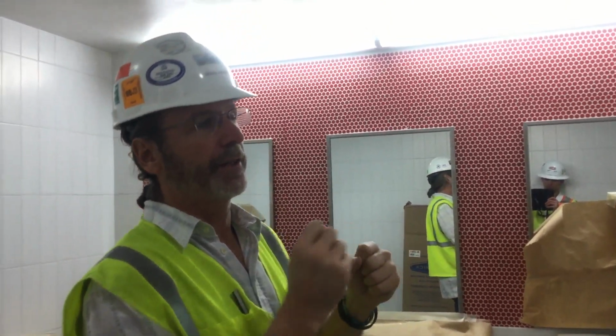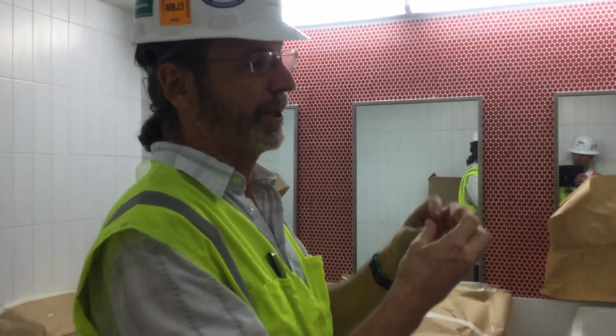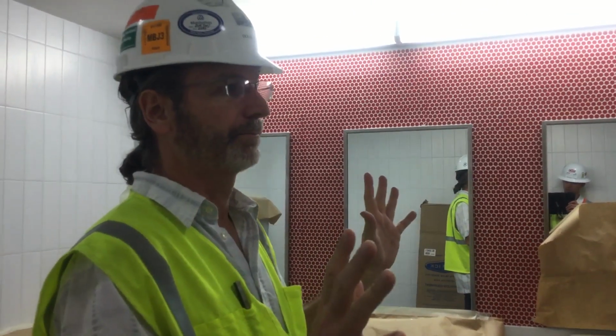That relay puts out - is there a light switch in the restroom? Yeah, that relay feeds to a standard toggle switch and then goes out, so the circuit's a little different. If the switch is on, the sensors run the light; if the switch is off, the lights are out, circuit's broken. The power packs themselves are on a relay switch leg, which means if that relay ever turns off, this room's down, it will never turn on. So usually these aren't put on switch legs, that's why that relay will probably just stay on all the time.